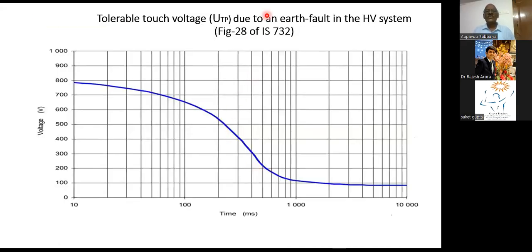What the standards prescribe is that you have to observe the tolerable voltage. If you can reduce the voltage, say to 600, then the tripping time should be less than 150 milliseconds. If you can reduce that touch voltage to 110, then you are allowed to have more than, say, 1 second. So depending upon the duration and the touch voltage, you have to observe this internationally adopted IEC tolerance voltage criteria. This is brought in figure 28 of IS 732 also.